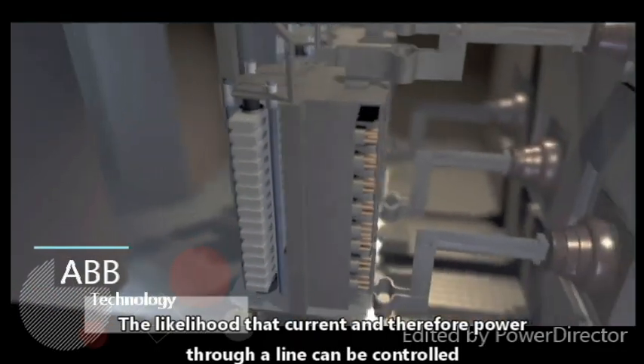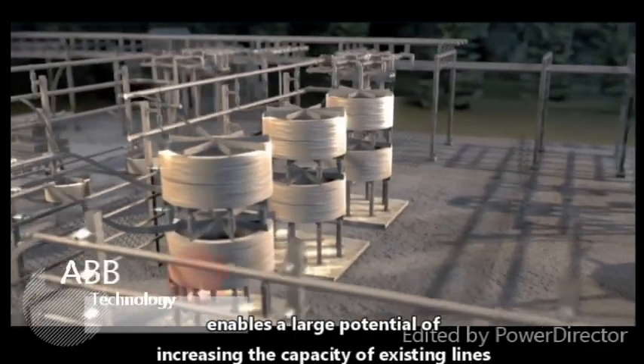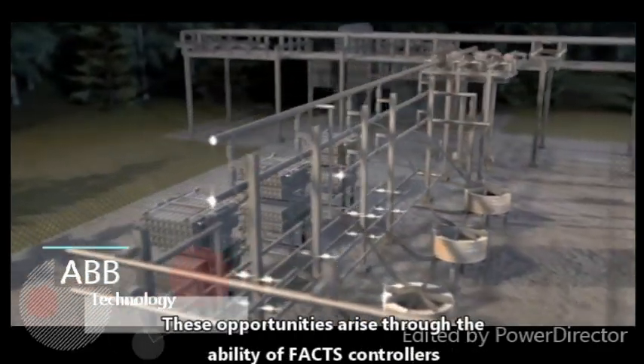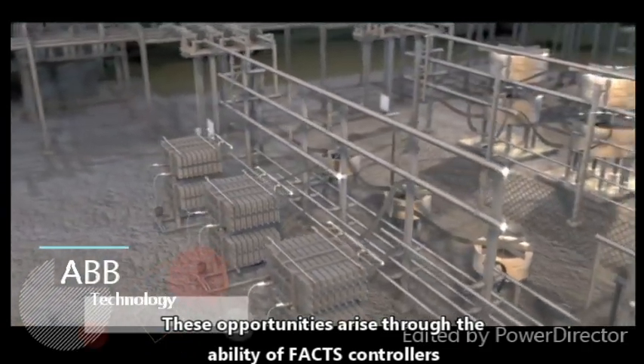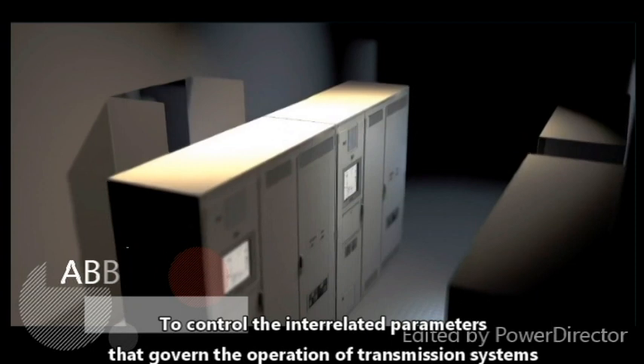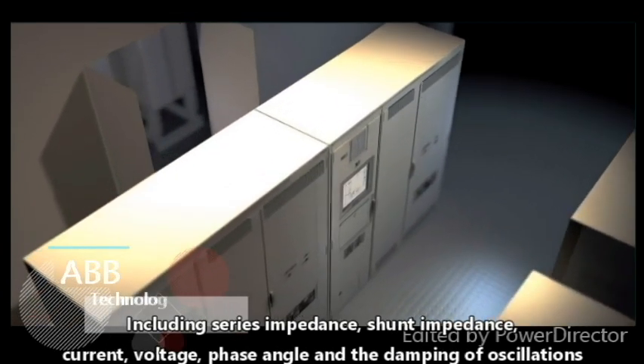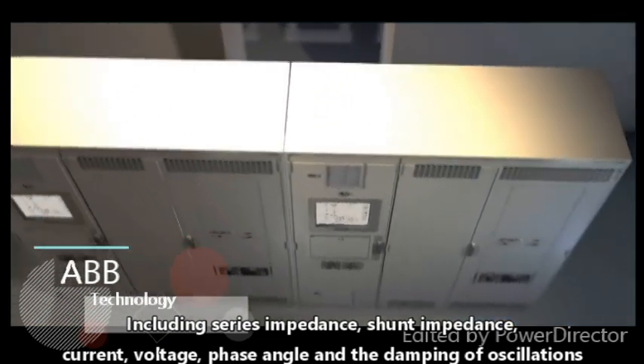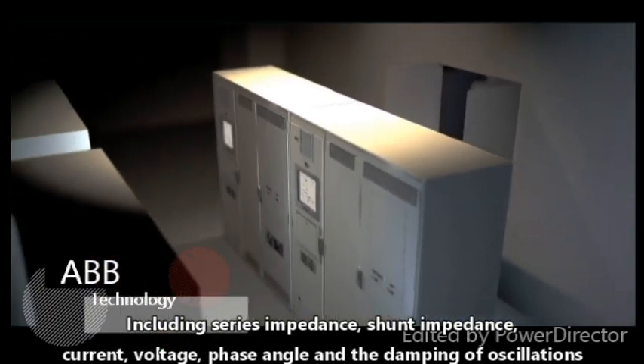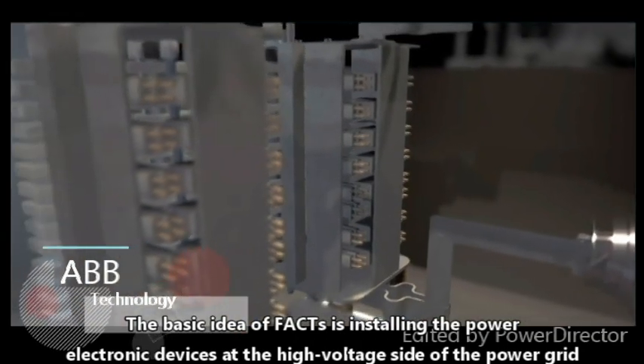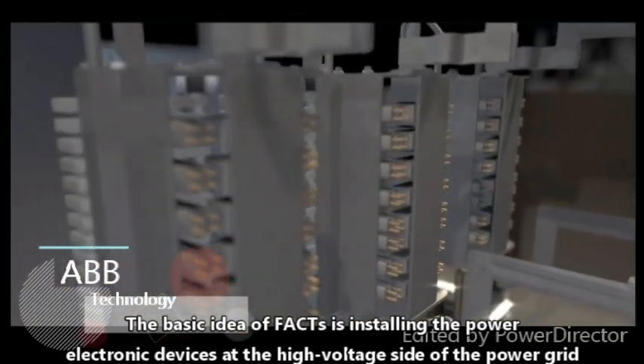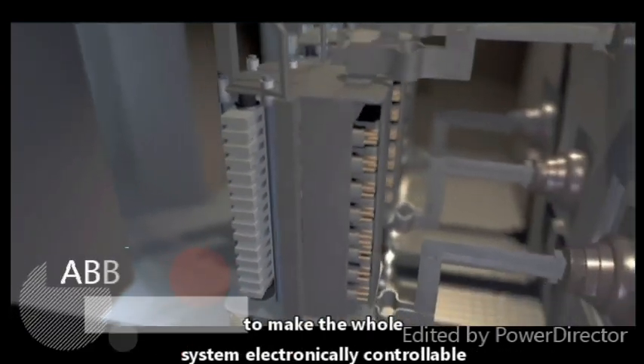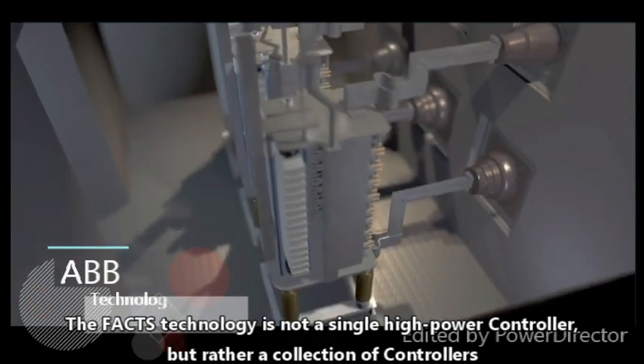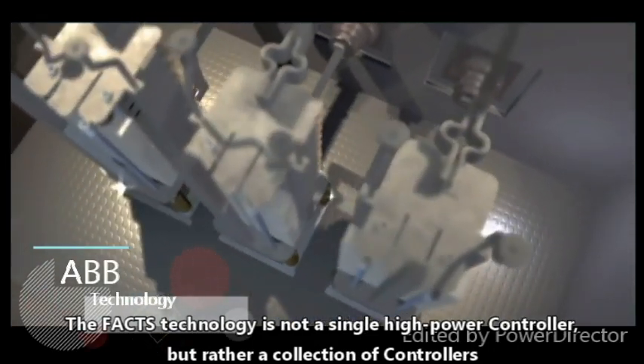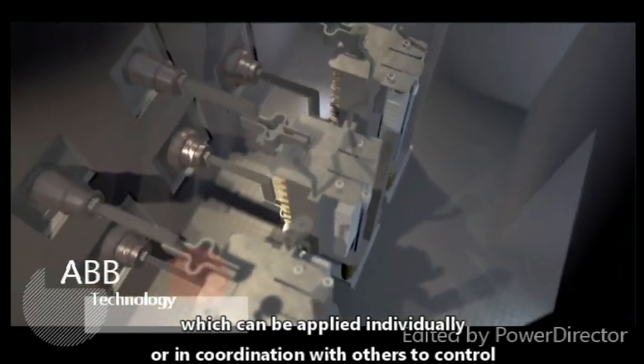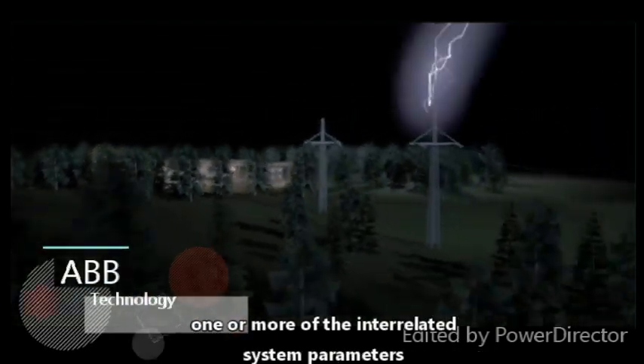The likelihood that current and therefore power through a line can be controlled enables a large potential of increasing capacity of the existing lines. These opportunities arise through the ability of FACTS controllers to control the interrelated parameters that govern the operation of transmission systems, including series impedance, shunt impedance, current, voltage, phase angle, and damping of oscillations. The basic idea of FACTS is installing the power electronic devices at the high voltage side of the power grid to make the whole system electronically controllable. The FACTS technology is not a single high-power controller, but rather a collection of controllers which can be applied individually or in coordination with others to control one or more of the interrelated system parameters.